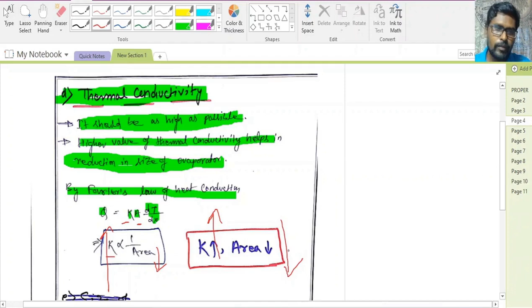A higher value of thermal conductivity helps in reduction in size of the evaporator. If the thermal conductivity is high, then the size of the evaporator will be less. It will not be a bulky system. We know from Fourier's law of conduction, Q is equal to K A dT by dx, where K is the thermal conductivity and A is the area. So if you increase the thermal conductivity, then the area requirement will decrease. That means we can reduce the size of the evaporator and condenser.